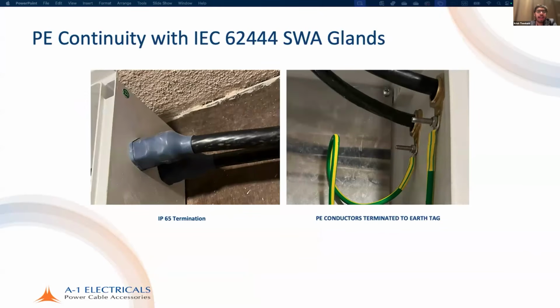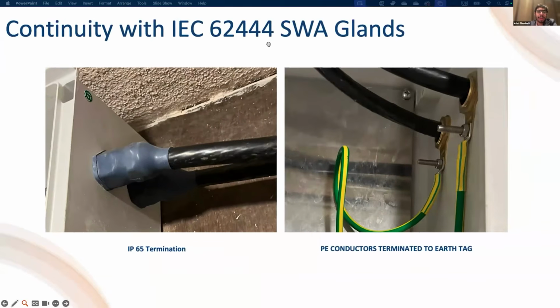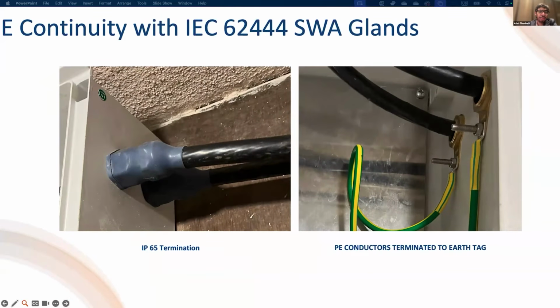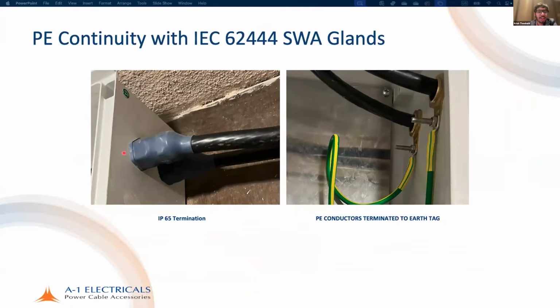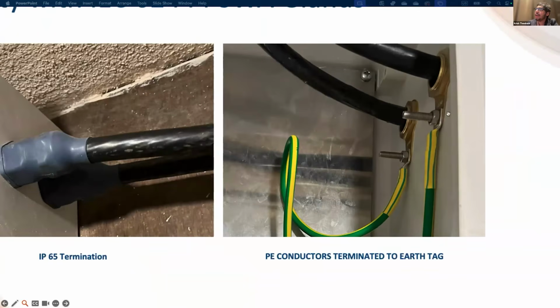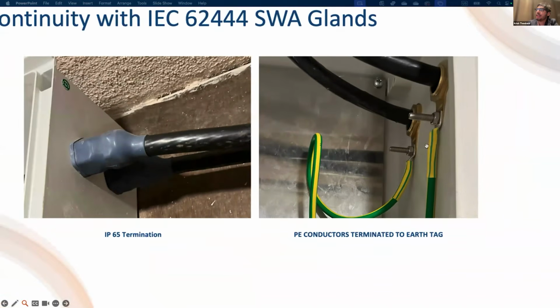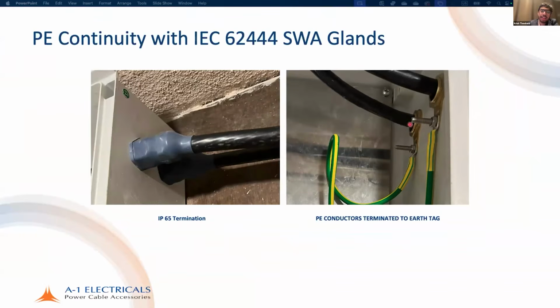When you use a gland that conforms to IEC 62444 and is designed for steel wired armored cables, firstly, you have a proper seal on the outside, and on the inside, you use this earth tag. You provide a lug, a nut, and a bolt, and you make a nice connection inside there. I have done this connection myself. It is particularly easy, and there's absolutely no problem in terms of the continuity. We get a very low earth fault loop impedance.